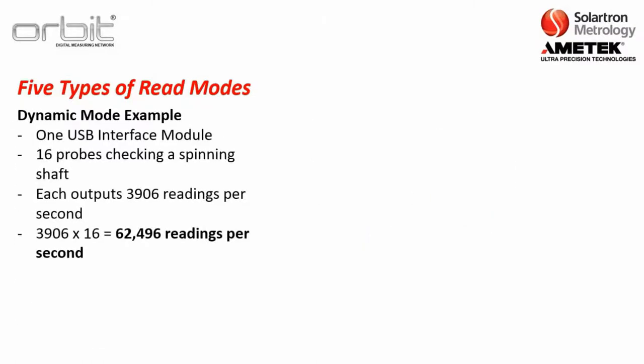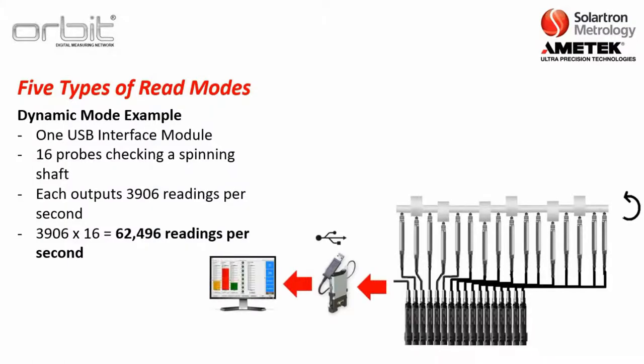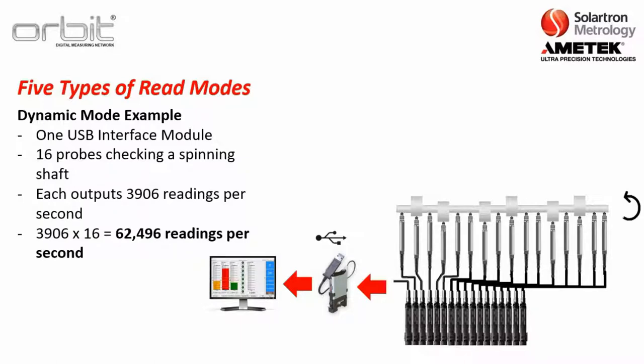Now, this is a dynamic mode example real quick. This is with the USB interface module. And you have 16 probes checking a spinning shaft like what you see here. Now, here, each particular module connected to a probe is outputting 3,906 readings per second. So, really, what you're having output to the computer through the USB interface module is 3,906 readings times 16 modules, or about 62,496 readings per second. So, it is a high-speed interface network.